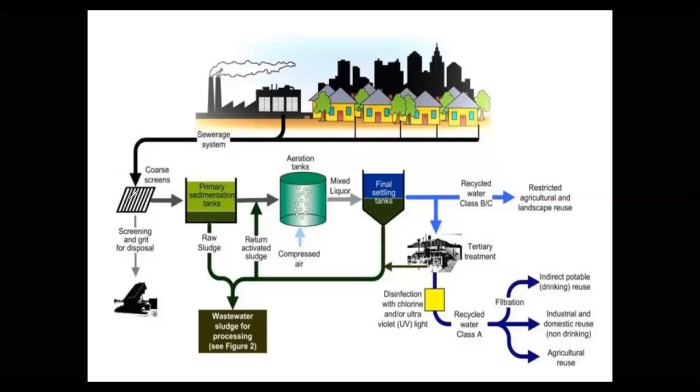Okay, now this is the way the wastewater plant is started. Every wastewater treatment plant should have the first unit operation as a screening process. Here you can see this is the screening. A coarse screen can be used to remove the larger size particles, and the removed particles can be crushed and recycled into the same water, or sent for solid waste disposal. Then the sewage will go to the primary sedimentation tank.